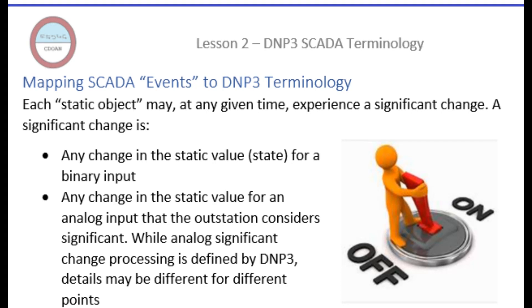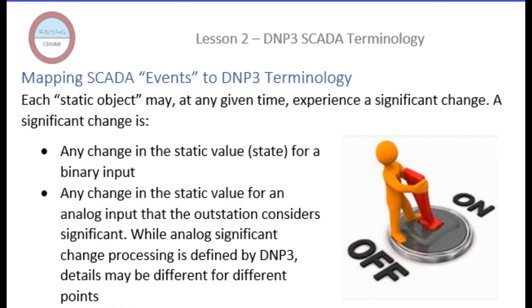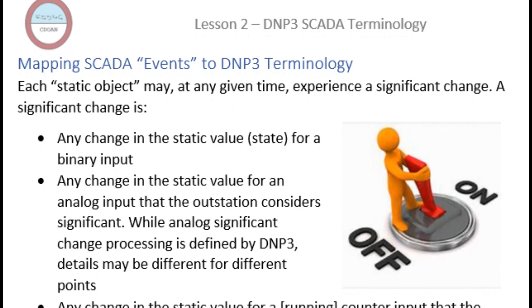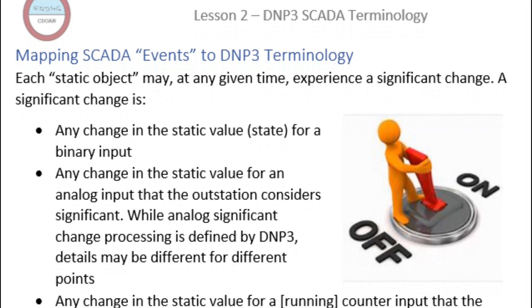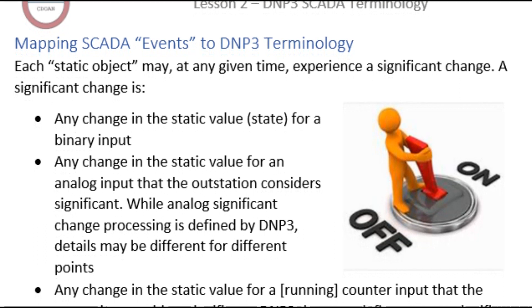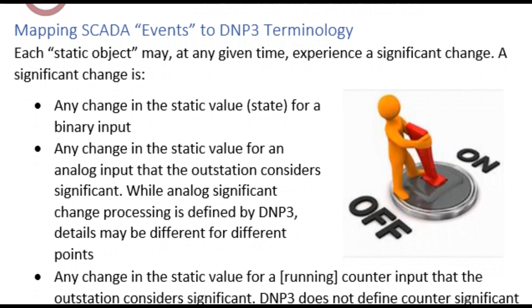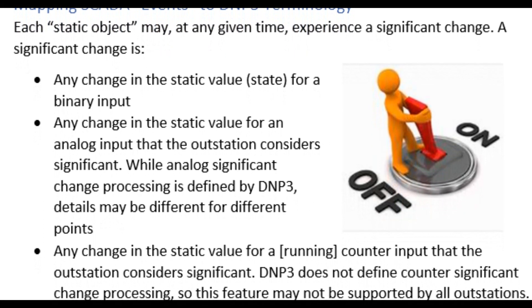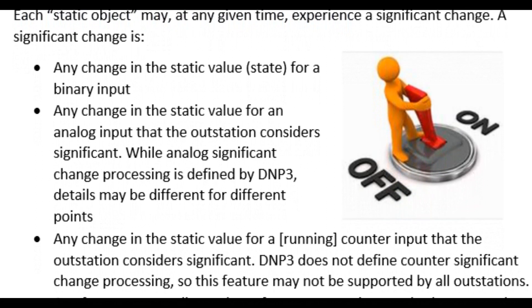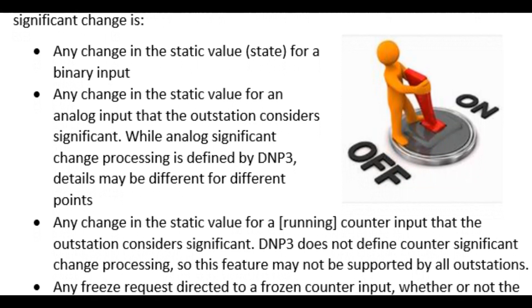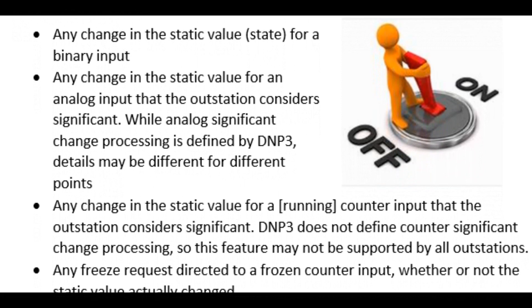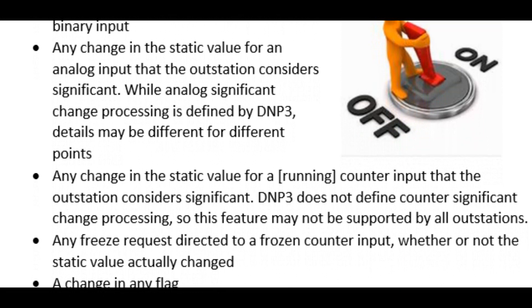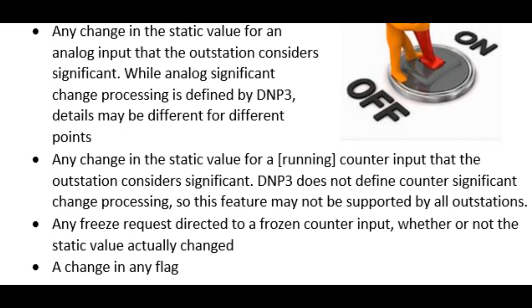Each static object may at any given time experience a significant change. A significant change includes: any change in the static value or state for a binary input; any change in the static value for an analog input that the outstation considers significant (as defined by DNP3); and any change in the static value for a running counter input that the outstation considers significant. Note that DNP3 does not define counter significant change processing, so this feature may not be supported by all outstations.